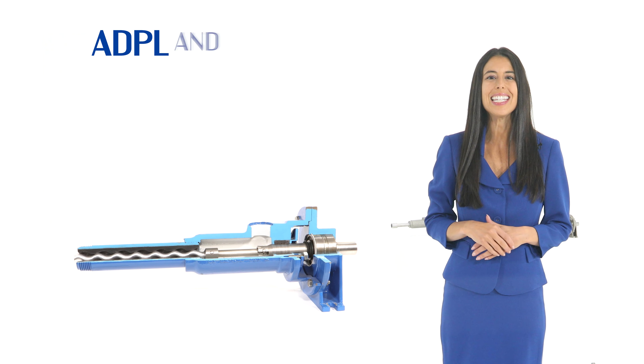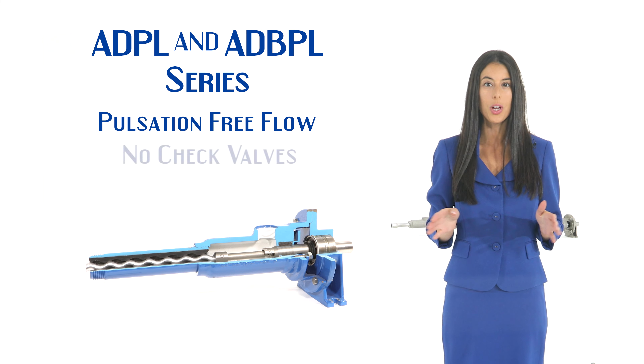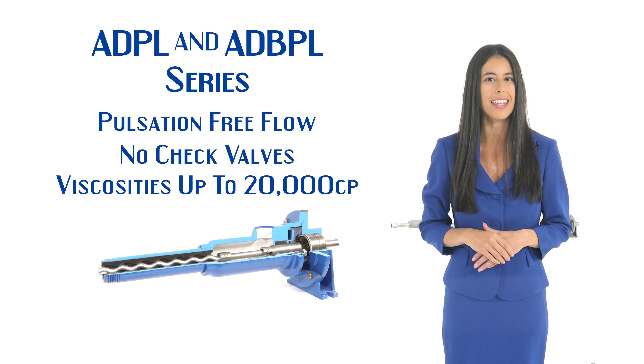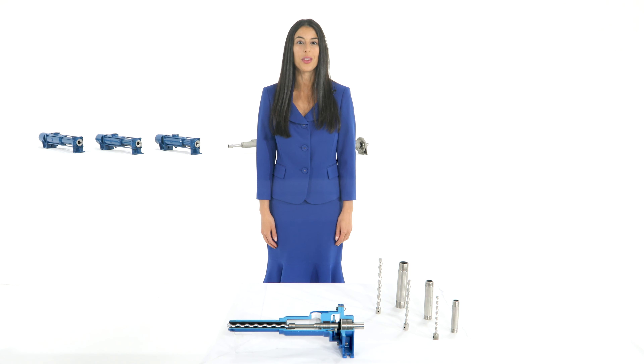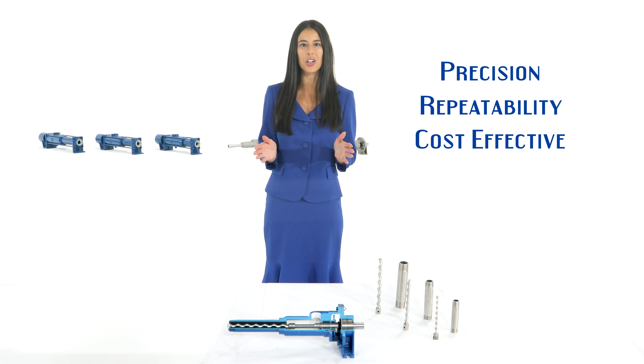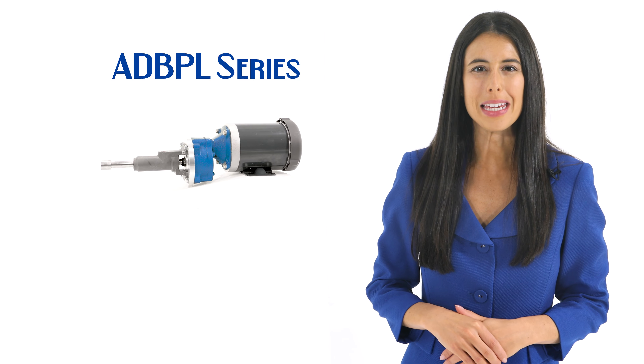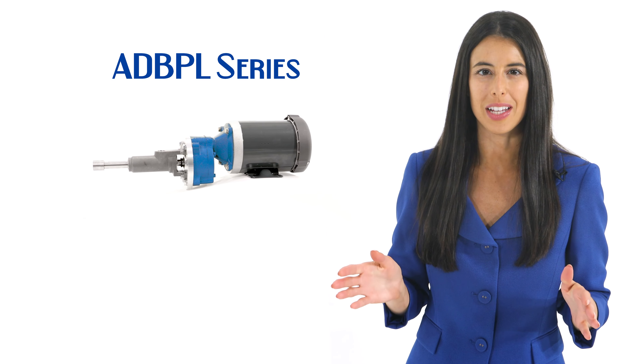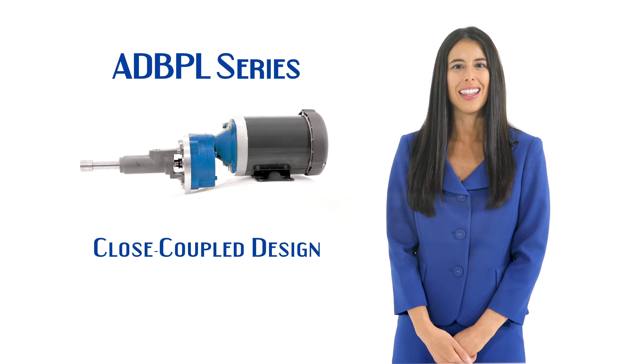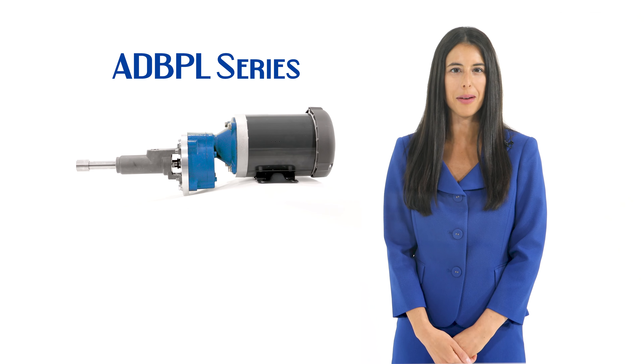The Liberty Process ADPL Series of Progressive Cavity Metering and Dosing Pumps offers an ideal solution for many low-flow pumping applications that require high-accuracy and volume control at an affordable price. This pump is rated up to 0.95 GPM and standard discharge pressures up to 175 PSI in our two-stage design. For liquids that are low to high viscosity and abrasive, it provides a pumping solution that is much more reliable than other types of metering pumps available on the market today.